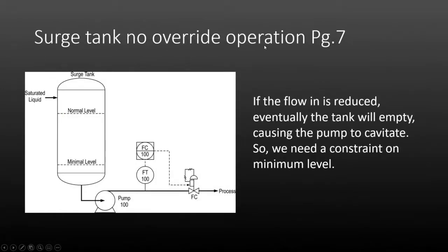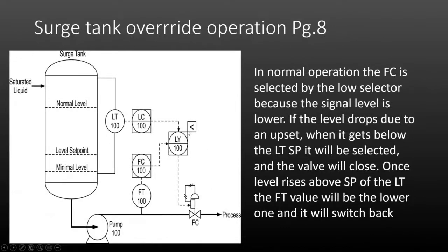Here we have a surge tank with no override operation. If the flow coming into the tank is reduced, eventually the tank is going to empty, causing the pump to cavitate — and that would be a problem. We need some type of constraint to ensure we maintain minimum level. To implement a selective strategy, we take a low selector, put it in the flow loop, and connect it with the level loop.